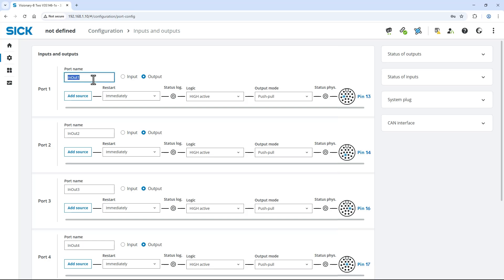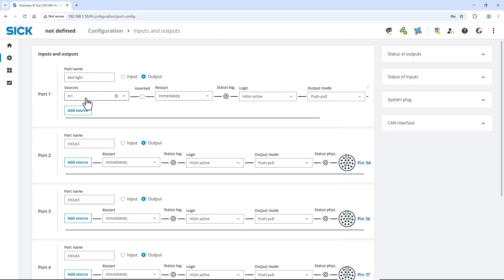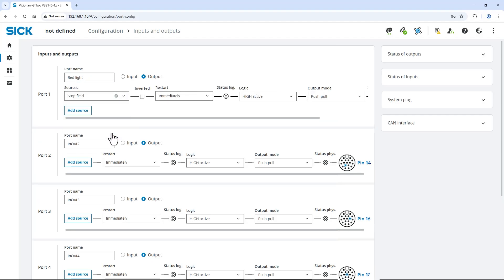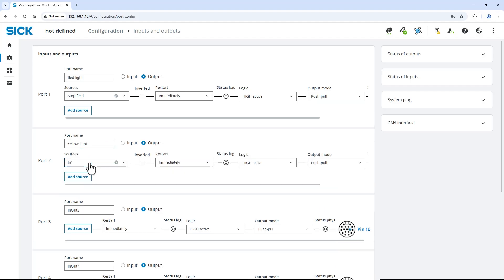Here you can link various sources to digital outputs or react to digital inputs, with many straightforward options to adapt the signals as needed. Change the port name of port 1 to red light. Click the add source button and select the source stop field. Rename port 2 to yellow light and choose the source warning field.